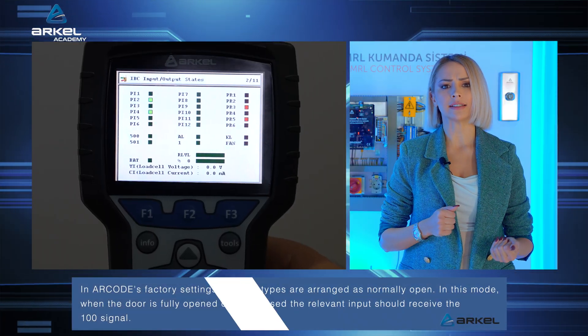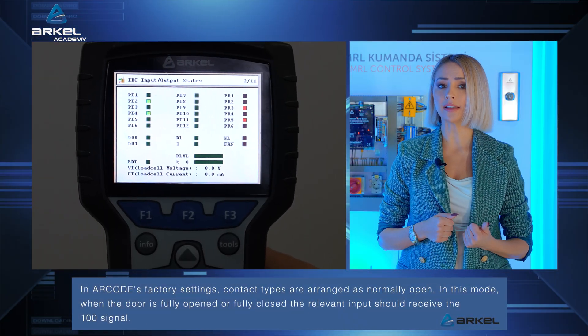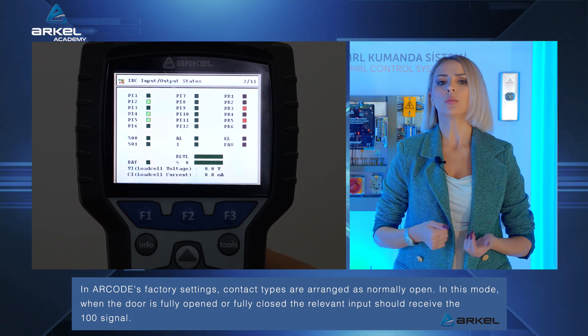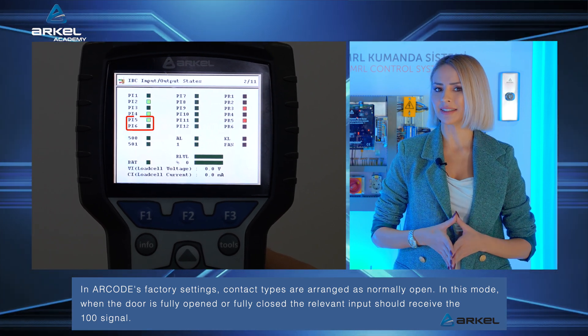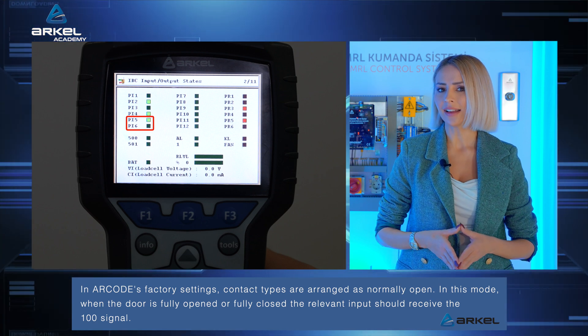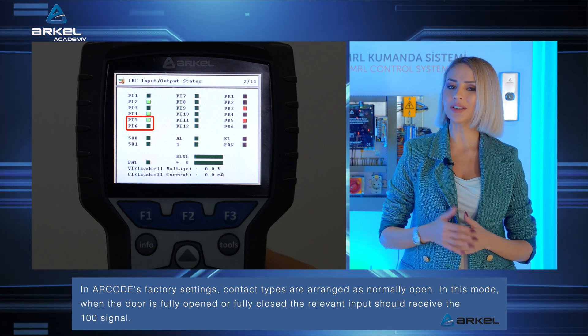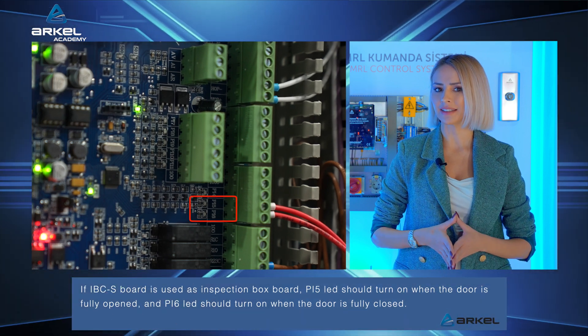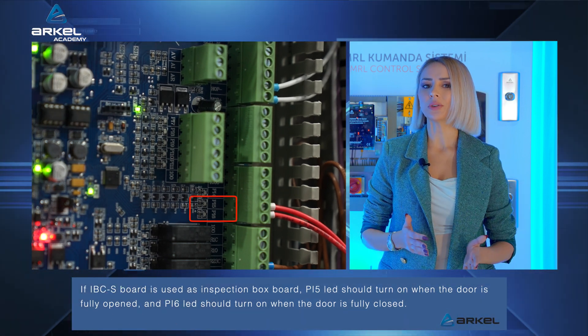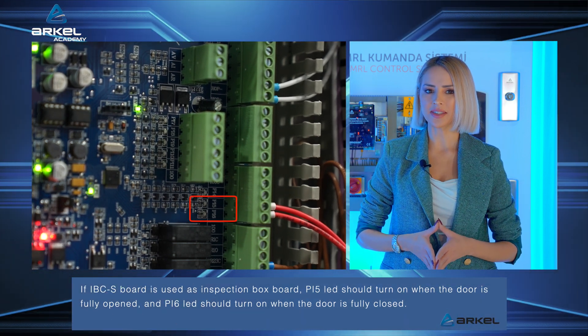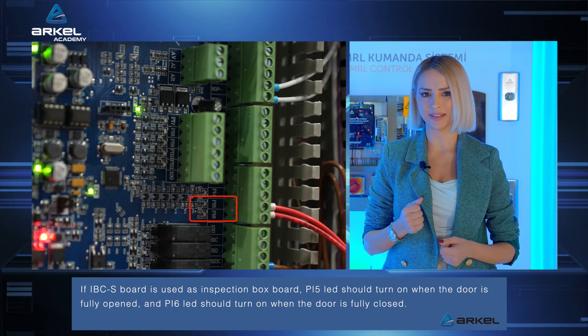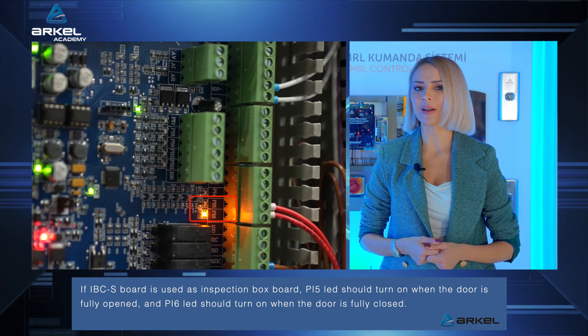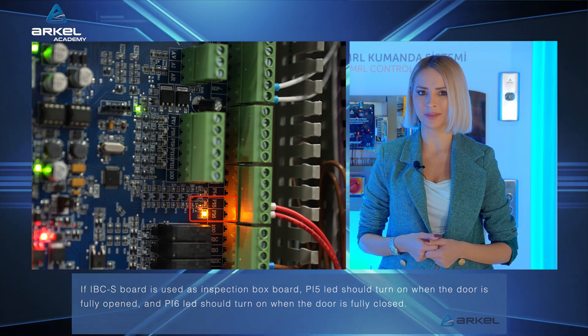In ARCODE's factory settings, contact types are arranged as normally open. In this mode, when the door is fully opened or fully closed, the relevant input should receive the 100 signal. If the IBCS board is used as inspection box board, the PI5 LED should turn on when the door is fully opened, and the PI6 LED should turn on when the door is fully closed.